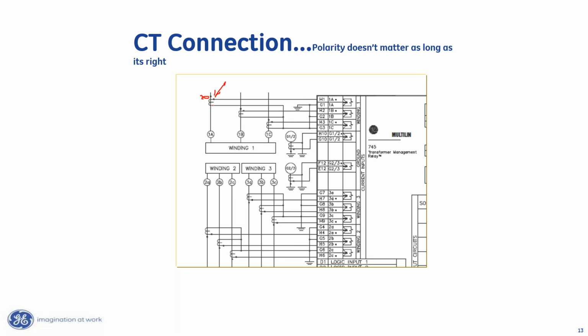So this transformer, for example, you look at all these windings, the polarity dots are away from the equipment. But let's pretend for a moment that we've got a breaker sitting down here. Now, normally in a differential, you'd want to include as much equipment as you can into the differential zone of protection. So that's where I draw that arrow down there. That's where you'd normally want your CT, so the breaker's in there. But let's imagine for just a moment that you wanted to use this set of CTs right here. The equipment manufacturer would put the dot right here.